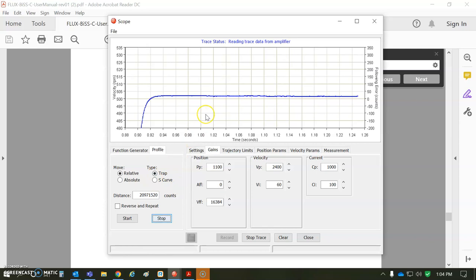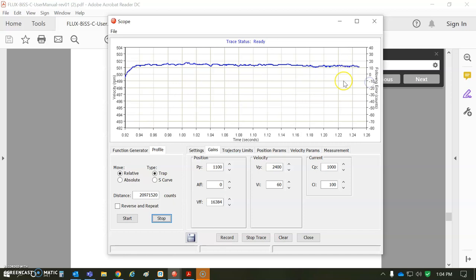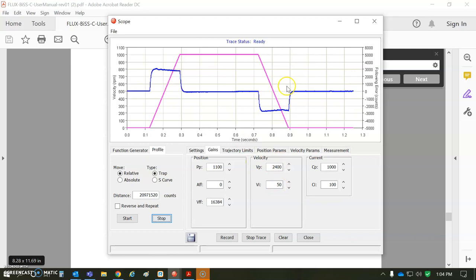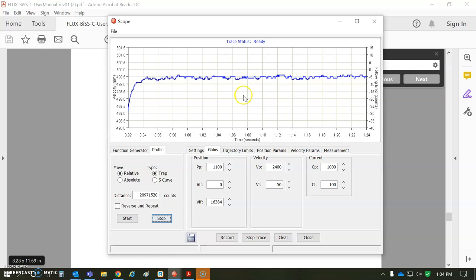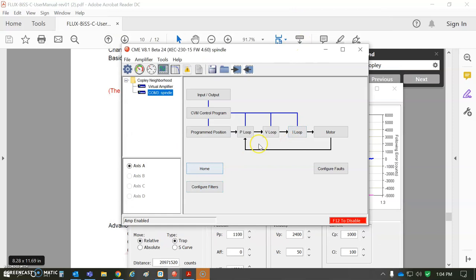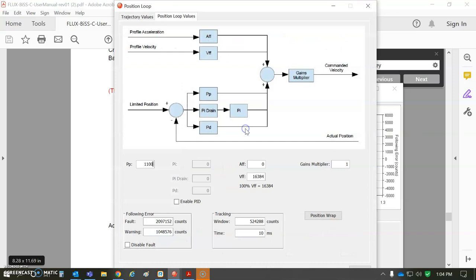So I'm moving and settling within 10 counts, and I'm just tweaking it a little bit here. When you have a big inertia, you're going to come back and adjust this anyway, depending on how big the inertia is. Within five counts—if you had to wait before you got to a certain resolution before you could do a cut or something, you could reduce the tracking window down to like 100 counts, 10 counts for a short period of time, depending on how long.